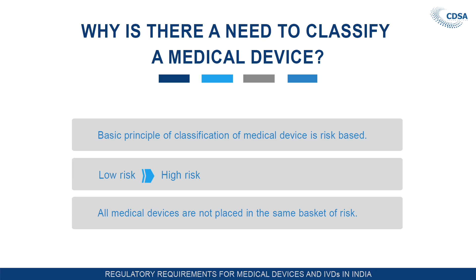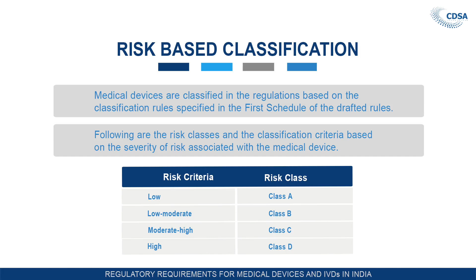Risk-based classification. Medical devices are classified by the regulations based on classification rules given in the first schedule of the rules. I won't say drafted over here because the rules have already been published. Following are the risk classes and the classification criteria based on the severity of risk associated with the medical device. Risk criteria: low is class A, low moderate is class B, moderate high is class C, and very high risk medical devices are class D.